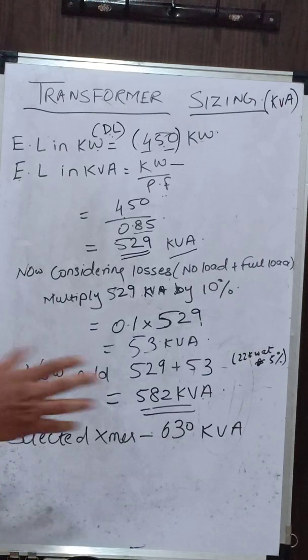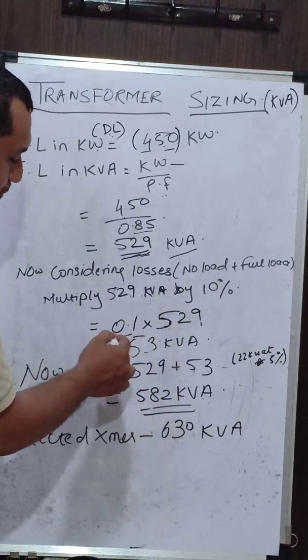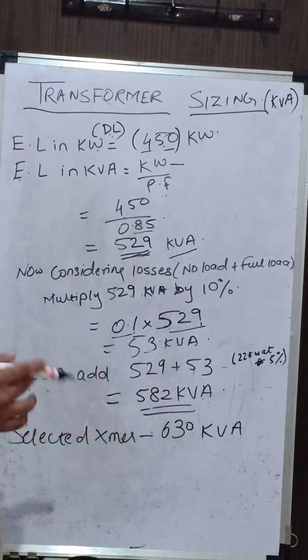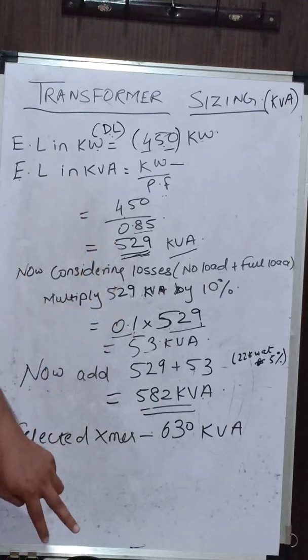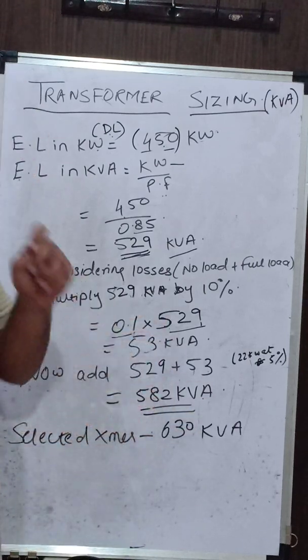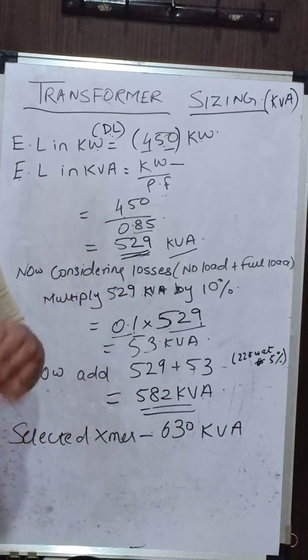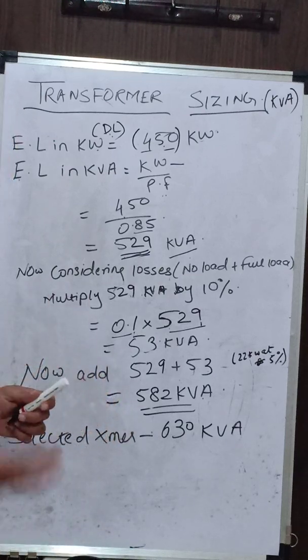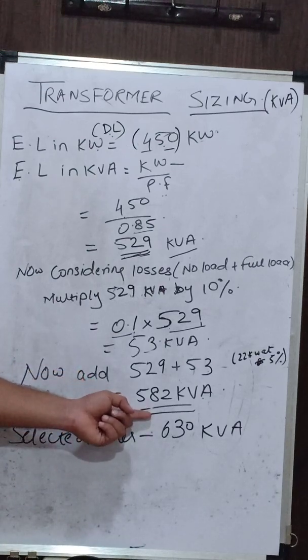For proper design, you must account for losses upfront. Multiply the existing 529 kVA by 10%, which gives 53 kVA. Add this 53 kVA to the original 529 kVA, giving a total of 582 kVA. This means a 582 kVA transformer will be sufficient to feed a load of 529 kVA while also covering the losses — since 53 kVA is absorbed by transformer losses.